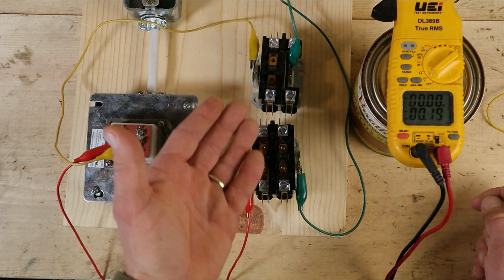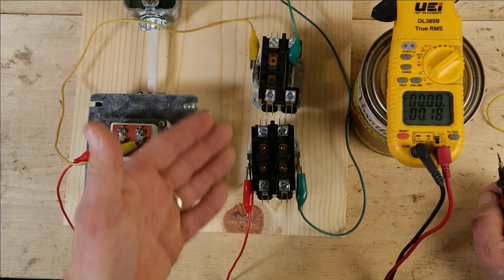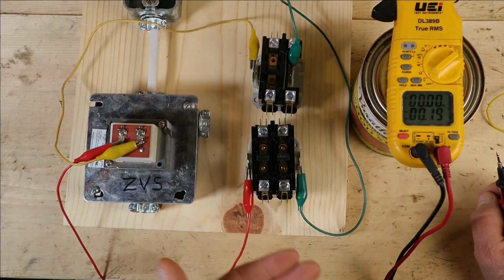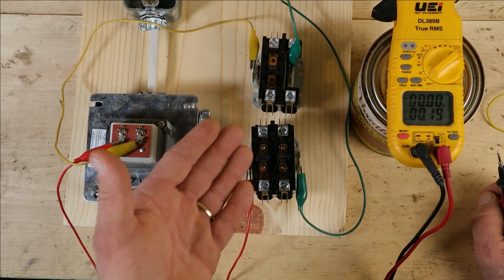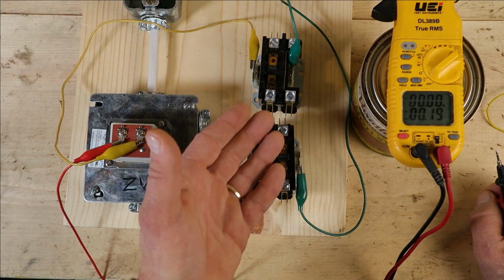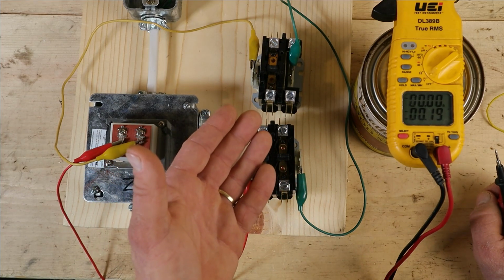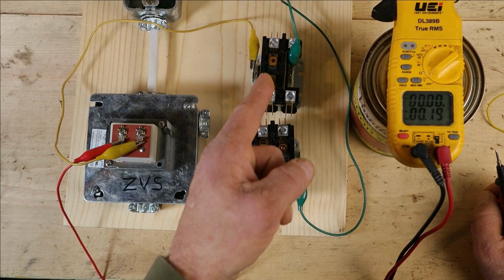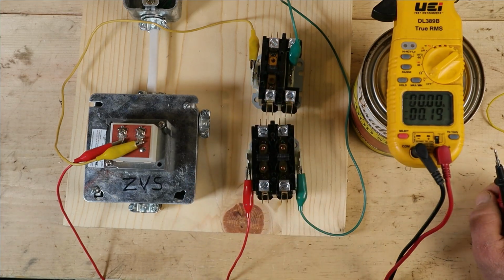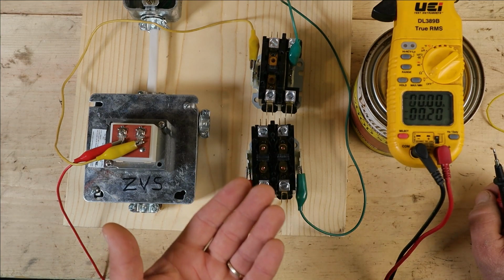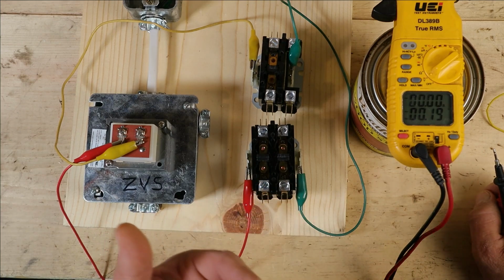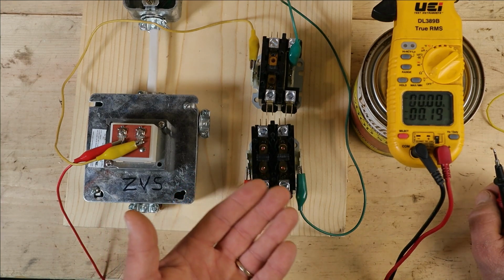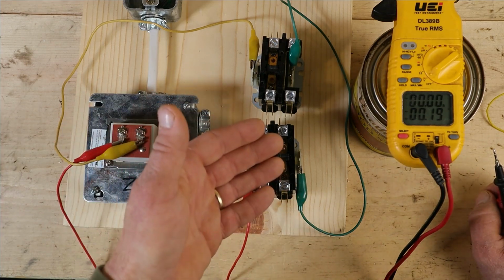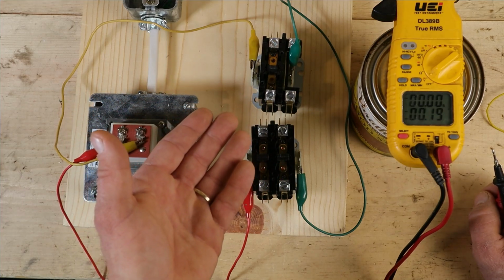Now, you're obviously not going to see 2 contactors wired in series like this in the real world. I did this on purpose to prove a point. But there are natural things that can happen in a circuit that can mimic the same results we're getting by adding a second contactor. This would be things like rusty terminals, loose wire connections, corroded and pitted contacts, and things of that nature.